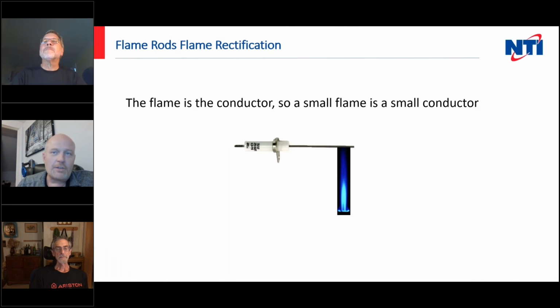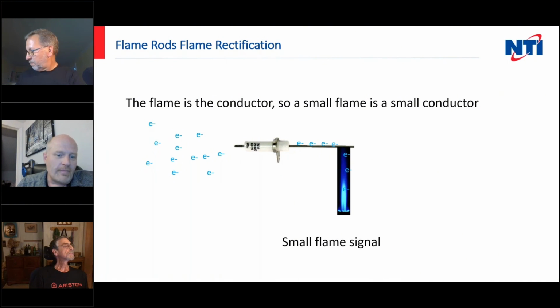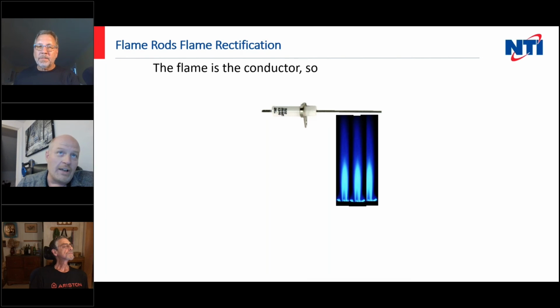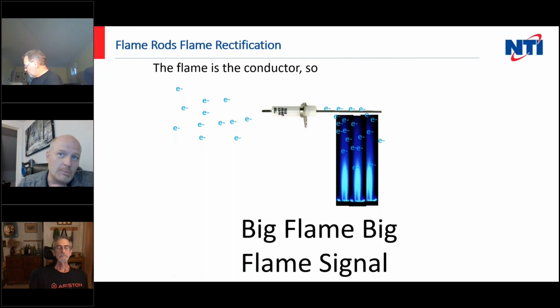So how does our flame affect our flame signal? Well, the flame is the electrical wire. So small flame, just like having a small wire, can't conduct very much electricity. And what ends up happening is you get a small flame signal. If you have a big flame or a healthy flame, it means that you've got a bigger electrical conductor, which means more flame signal, more electrons move back and forth.